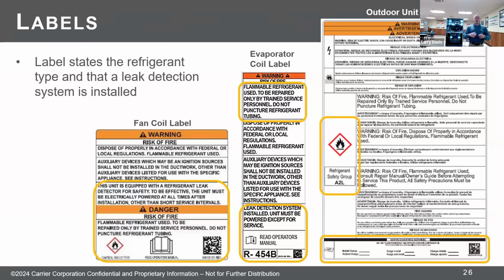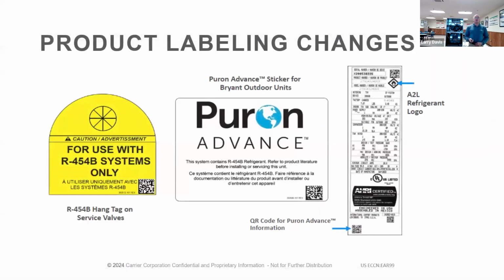Labeling, you're going to see a lot of difference in the labeling where it's going to say that there's a refrigerant that falls into the A2L group. It's going to have a little flammability symbol on there. That's just a reminder on all the equipment. Again, indoor unit and outdoor unit both have to be 454B rated. Okay. Here we see again just some different hang tags and the different labels that are going to be on the system. You see the QR codes. If you haven't used those on our products, if you're out working on a system, you can scan that QR code and it'll pull up the installation information for that unit.